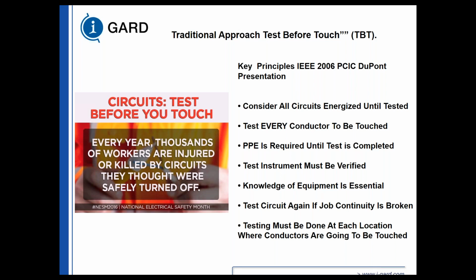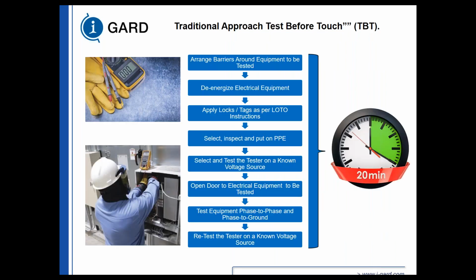I've been to many electrical safety workshops, and it's astonishing to me how many times people run into difficulty, and even if they just need to go and get another tool and come back, they should always re-verify that the gear is de-energized before going in. A countless number of accidents and fatalities have occurred because people have gotten into the wrong cell. And so this is very important, and this becomes part of awareness. Testing must be done at each location where conductors are going to be touched.